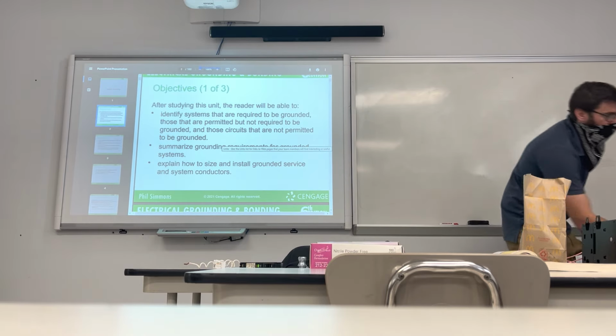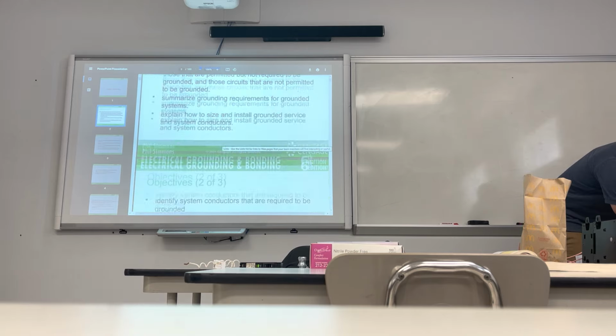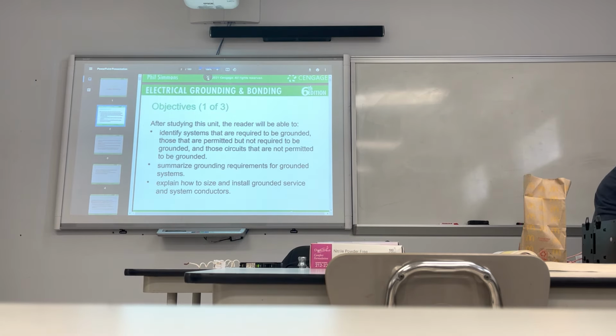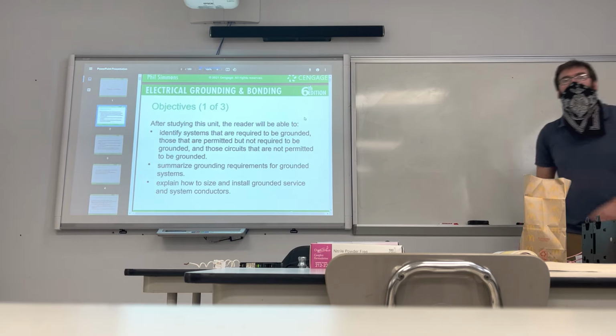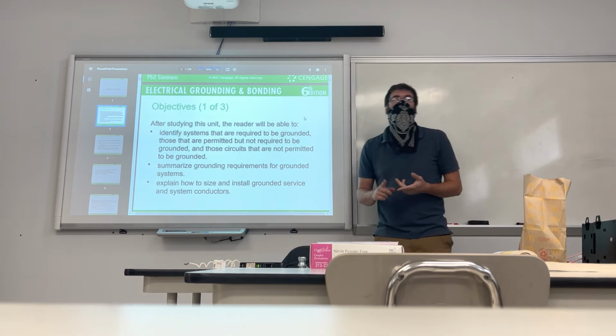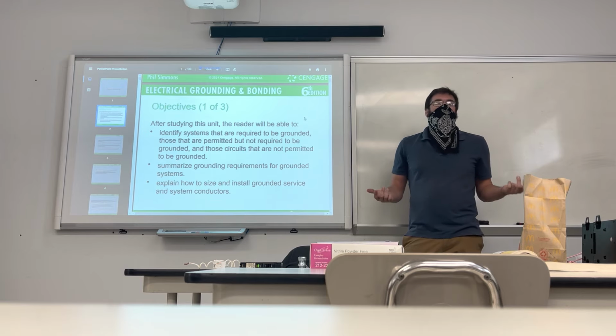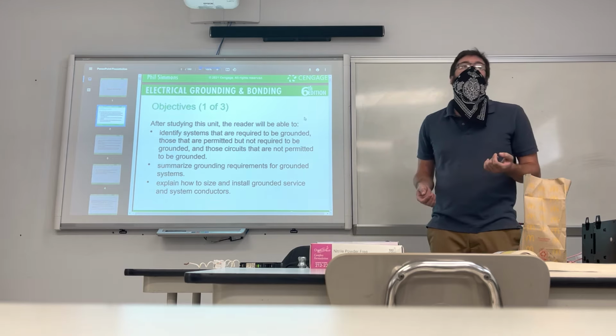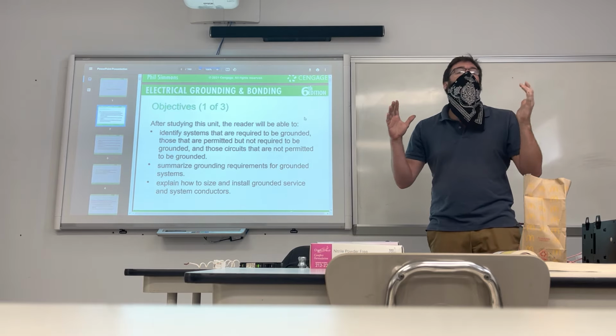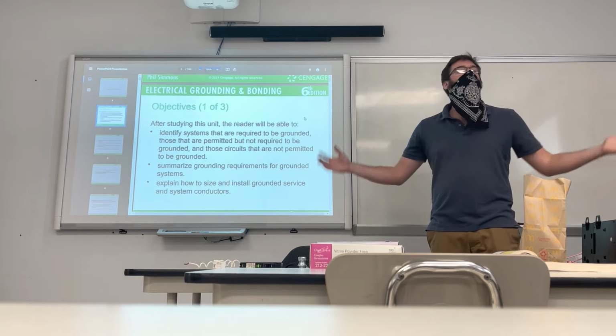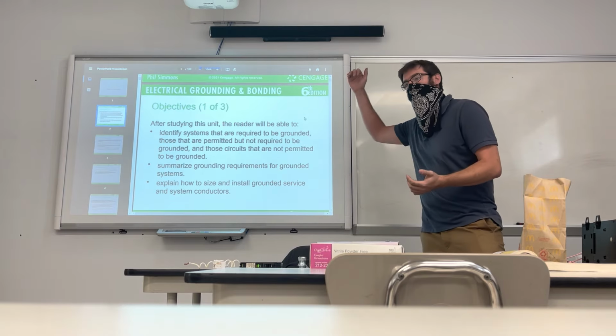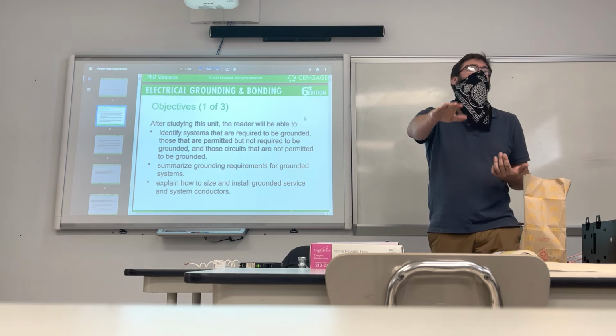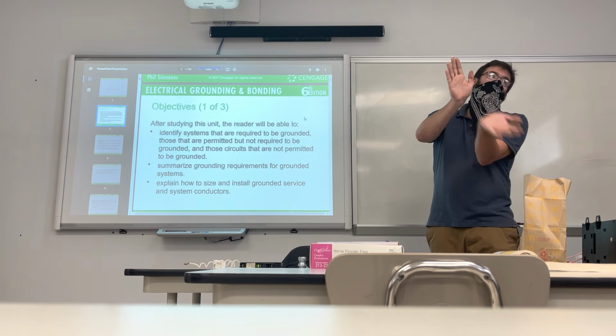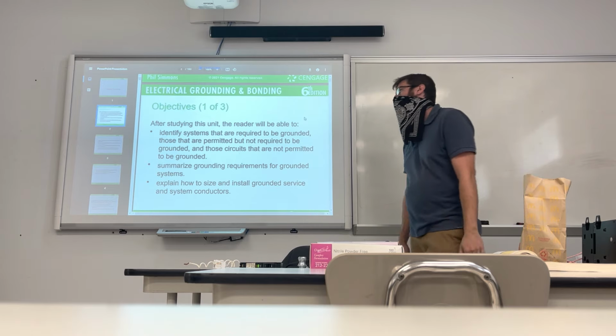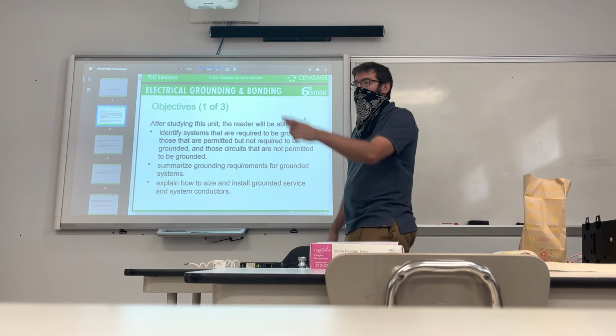And two, we've hit a lot of this information already, like in the introduction in Unit 1. Basically, we're just beating the horse dead. You know what I mean? Like you have to bond the neutral and the ground in the main panel box. Anywhere other than the main panel box, they're going to be isolated to allow that ground to head cleanly back to the main panel box, to head cleanly to either the neutral on the weatherhead or to the ground rod to dissipate that high voltage. So we're just going to continue with that, Phil.